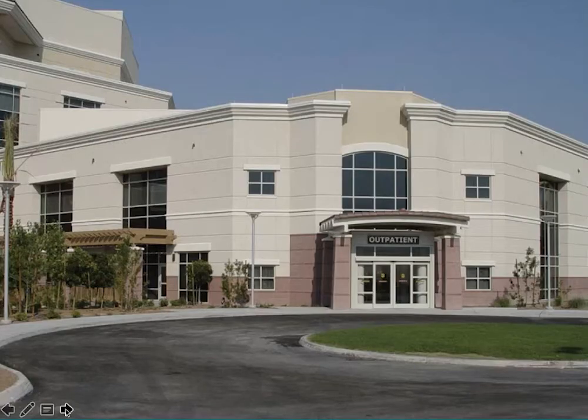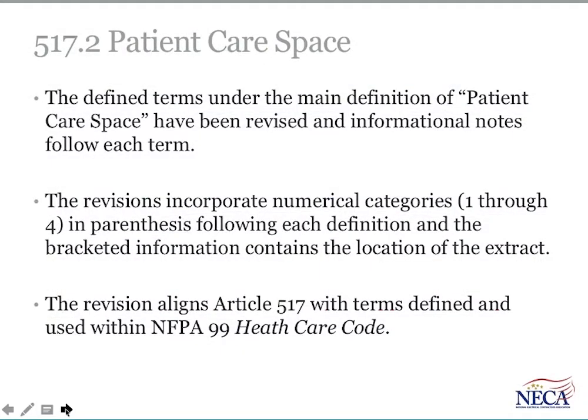An example of a healthcare facility. There's a definition in 517.2. It's a multi-part definition, and it was previously titled patient care locations. And one of the things you're going to see throughout Article 517 is that the word location and the word area, as in patient care location or patient care area, have all been changed to spaces, and the spaces have been categorized. So no longer do we use the phrase patient care area or patient care location. We use patient care spaces, and then we categorize them in categories 1 through 4 based on their hierarchy or level of care within each one of those locations.